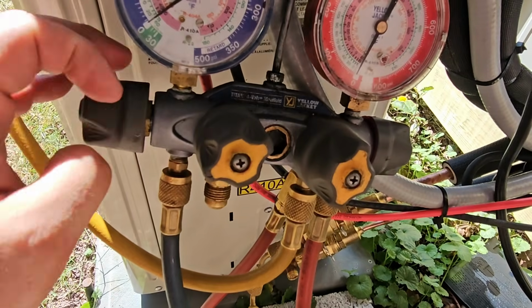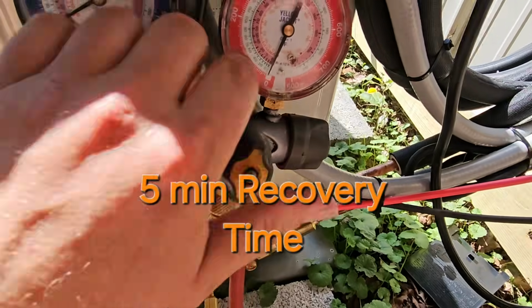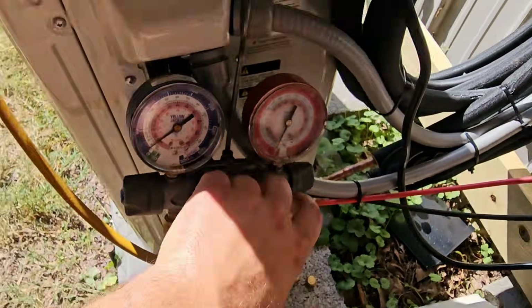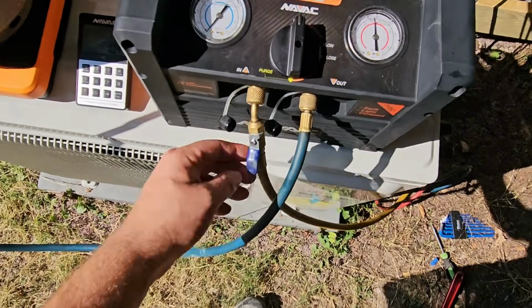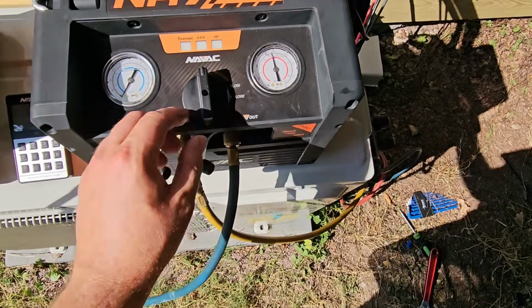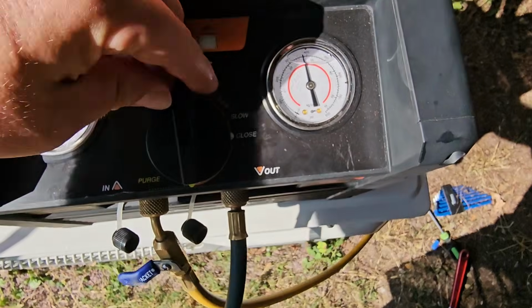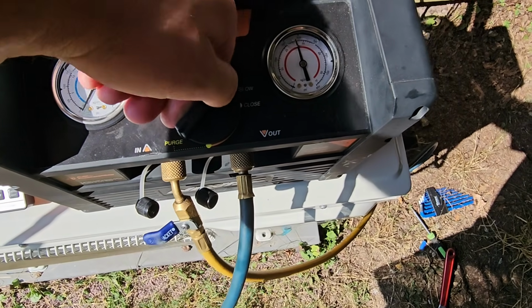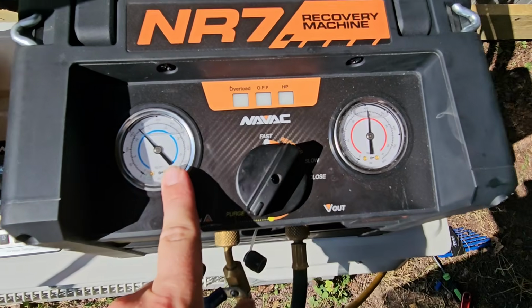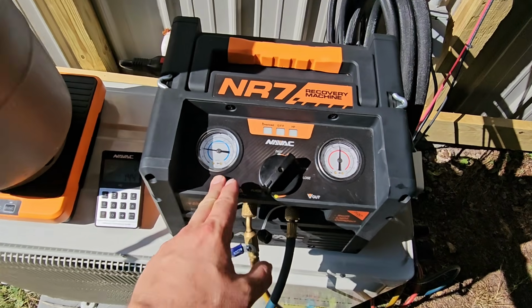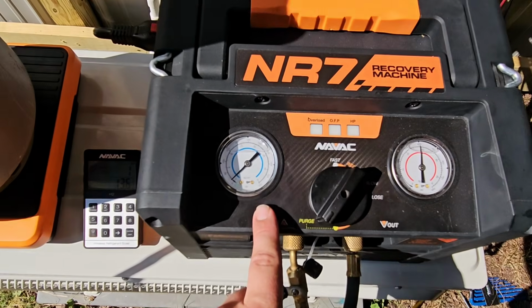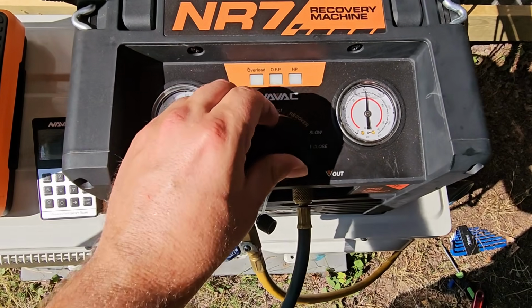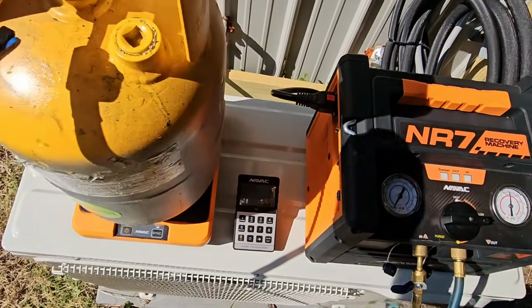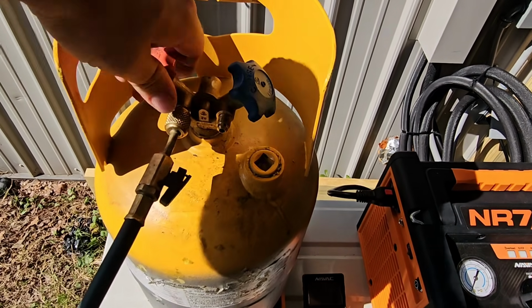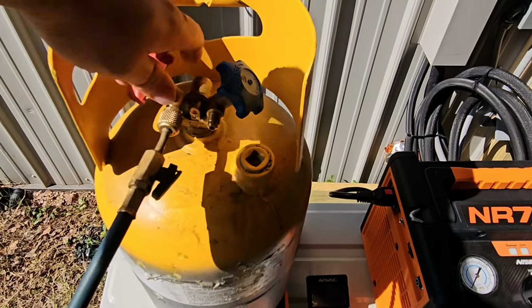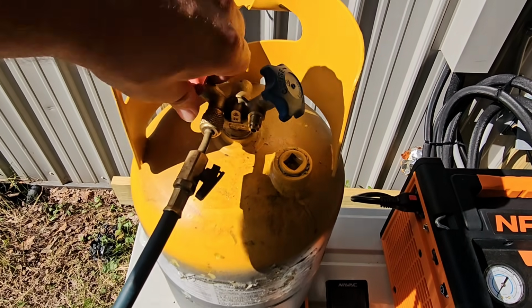So what we're going to do is close our gauges. And then we're going to close our line going into the tank or the recovery machine. And then we're going to turn the recovery machine dial to where it says purge. And it's going to purge what's in the machine into our recovery cylinder. And when it hits 0, you're going to close this, turn it off, and then we're going to close our tank like this. And you can close the tank first and then cut the machine off.